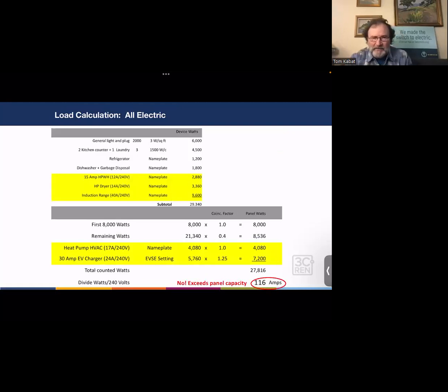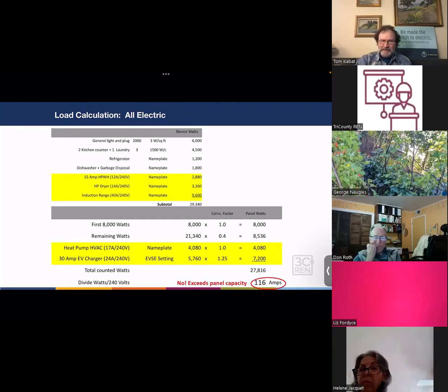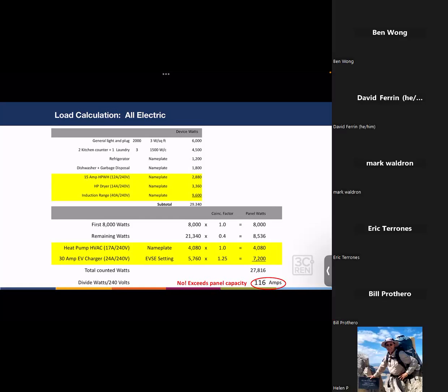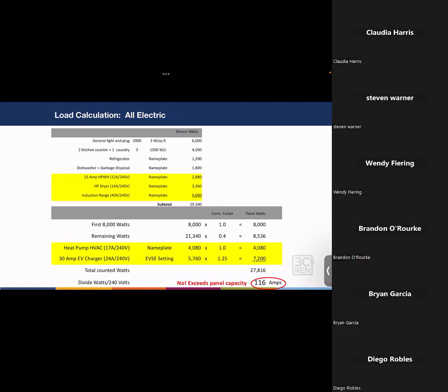And next slide. So changing that format to where you see the electrification items being added in yellow. Watts of those general loads are counted at 1.0 coincidence. The remaining 21,000 are counted at 40% coincidence. So that makes 8,500 counted watts. And then the two special cases, the heat pump at 100% coincidence has all 4,080 watts counted. And then the EV setting. So it's a 30 amp EV circuit flowing 24 amps, but the 24 amps is being multiplied by the 1.25 factor for a long duration load, a load longer than 3 hours steady, heating the wires and panels. So it counts as 7,200 watts.